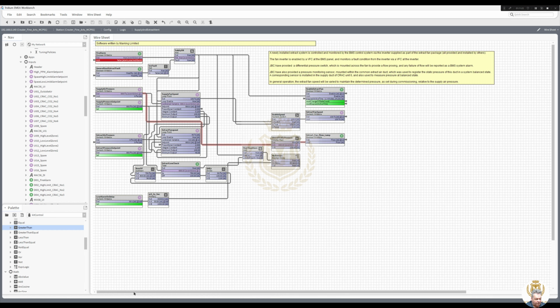So rename above static pressure, and I presume we do a static pressure. Duplicate static pressure value, set point. Got graphics to do on this as well. 200 actions set to 200, so it can be adjusted by the graphics when I do the graphics.